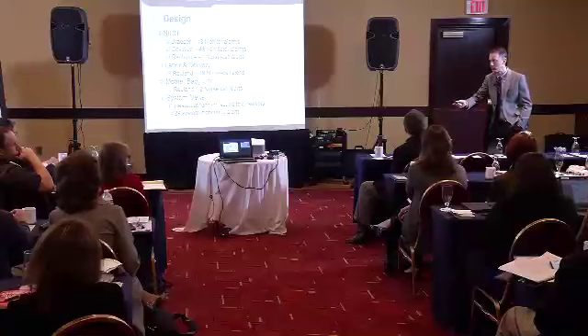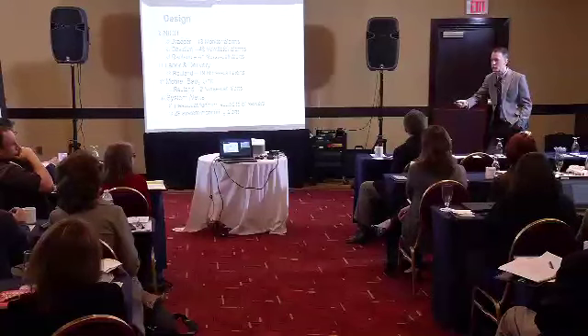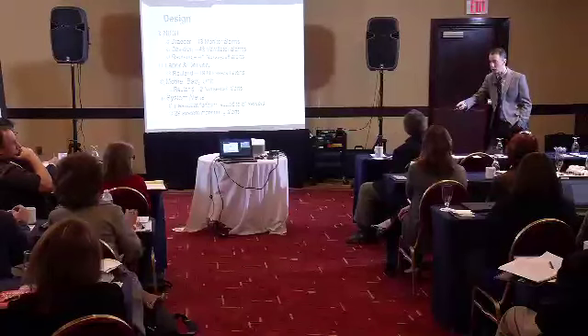So you really need to set those parameters for a very short time, because if you set it for 10 minutes, you don't want to know the system's down 10 minutes before it comes back up, because it only has to be down 1 minute and you miss a code blue.